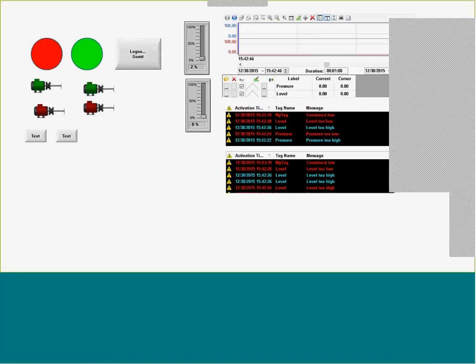And now let's clean here. You have a combined low, of course, in this case here, they are both very low. If I come to this one, 12, it's done, but the combined is still low. If I come here, now the combined is gone because the 9 plus 12 is higher than 20. So you can play with those two tags to have an expression, but you need to configure single tags in the alarm spreadsheet.